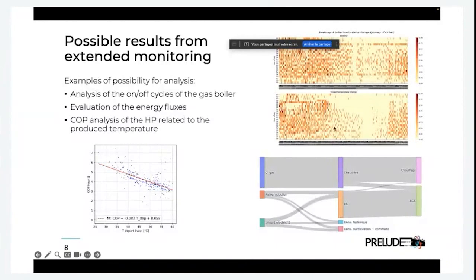Then we changed some parameters in the boiler instructions, meaning it would only produce heat if some threshold was met for the domestic hot water. We can see that the status changes are way lower now, meaning the gas boiler just turns on and off less than earlier, which is good for its life cycle.